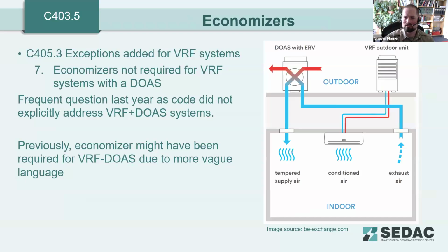Economizers, not a whole lot of change here, but a clarification update. In the 2018 IECC, the only exceptions for economizer installation were based on reduced operating hours for economizing or limited economizer benefit due to heat recovery or humidity control requirements. This resulted in a lot of questions from people about VRF plus DOAS systems. Did those require an economizer, even though they have energy recovery, and there's not a whole lot of benefit to an economizer on those systems? So the 2021 has specific language acknowledging that those VRF technologies are much more efficient and that an economizer has limited benefit. And so they are included in the exceptions for economizers.